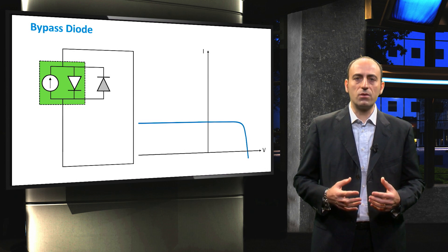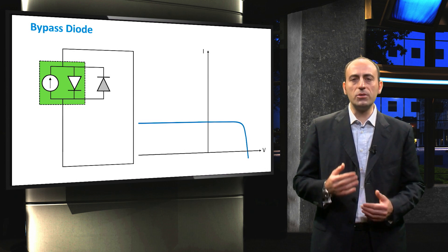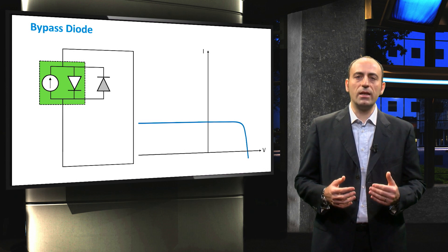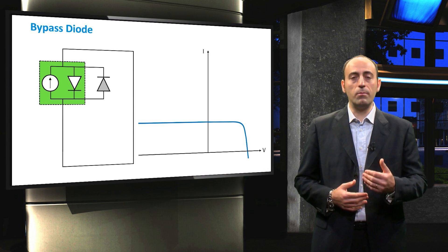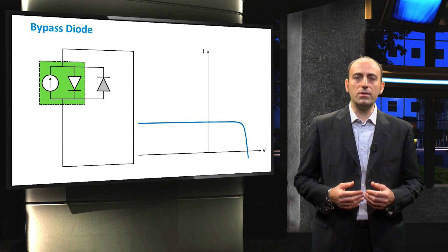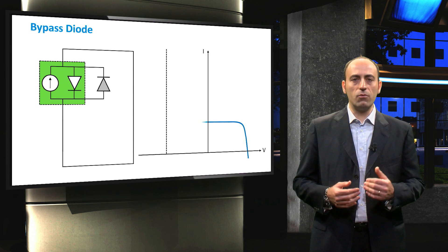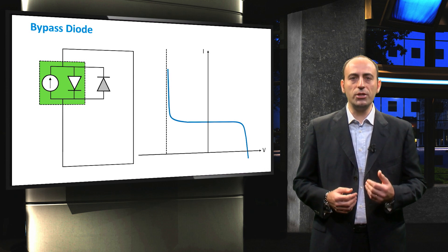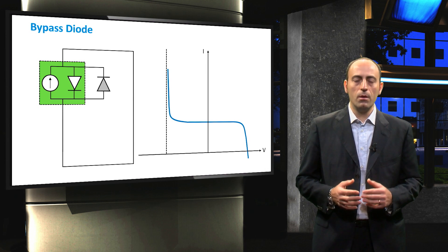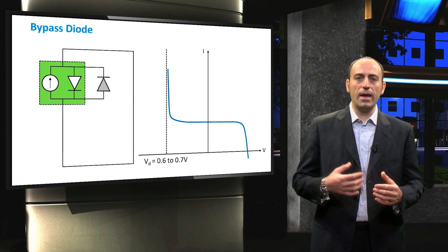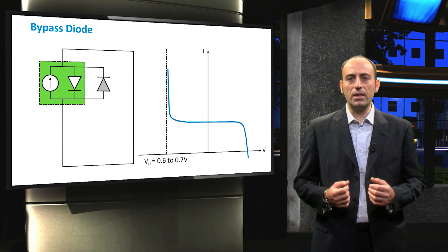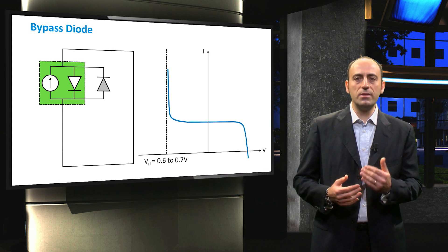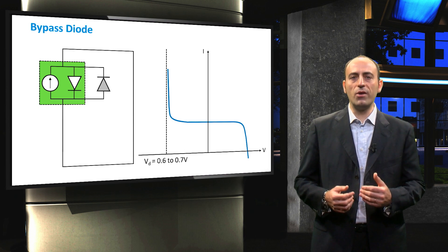Such a diode is connected in parallel but with opposite polarity with respect to the cell. This means that in normal operation, each solar cell is forward biased, while the bypass diode is reverse biased. In the graph, it is reported how the current voltage characteristic changes when introducing the bypass diode. Between 0.6 and 0.7V in negative bias, the bypass diode is activated and it will raise immediately the current, avoiding the breakdown of the cell.